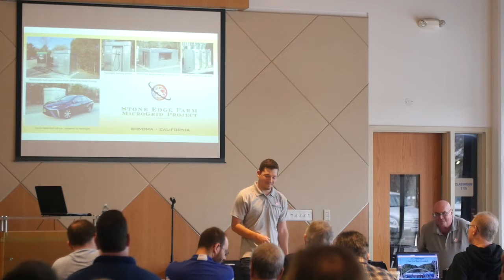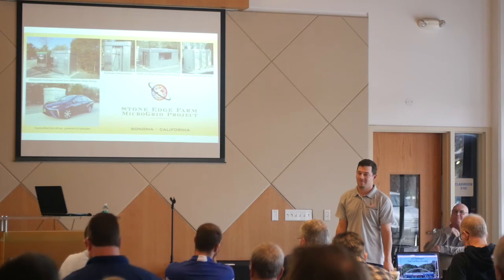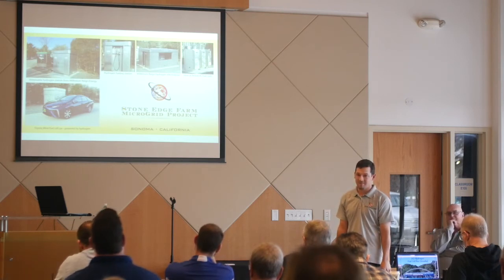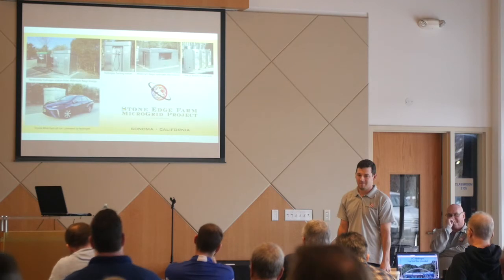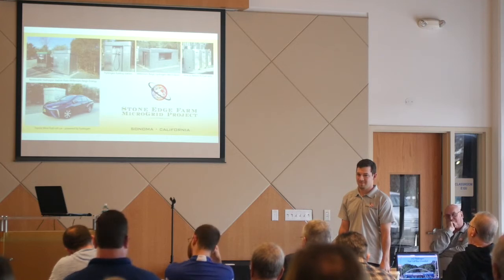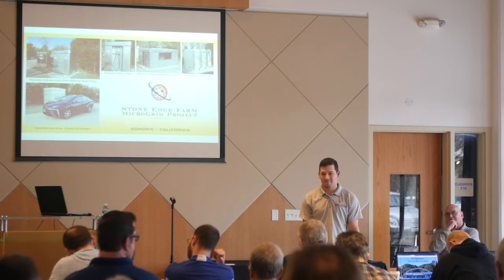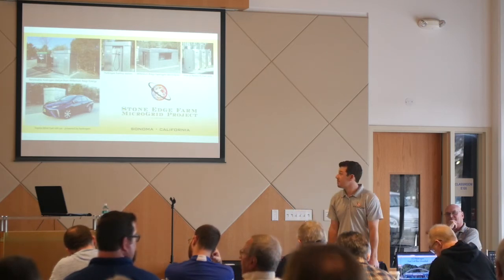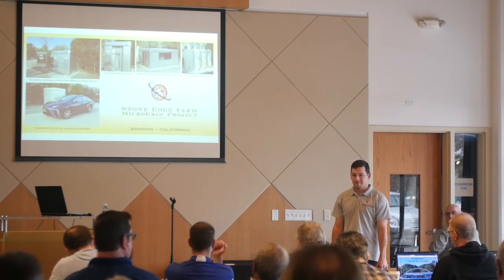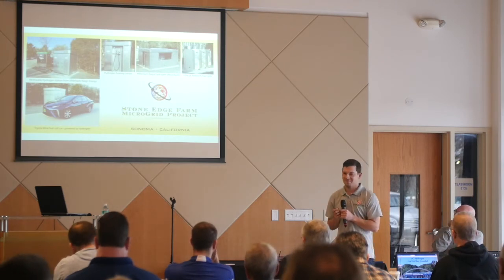It was briefly touched on, but I was curious. You're talking about microgrids, so obviously you're not doing net metering. You're making your own power and having to sync this power to a grid. Think of the grid as a very large ocean; you're basically syncing everything to the waves of the ocean. Where I'm net metering, I can't affect the grid's frequency, but in your case, you really can. You touched on the Tesla battery pack becoming your primary. What are you doing right now to tie all these little inverters and different systems together in order to maintain frequency and voltage?